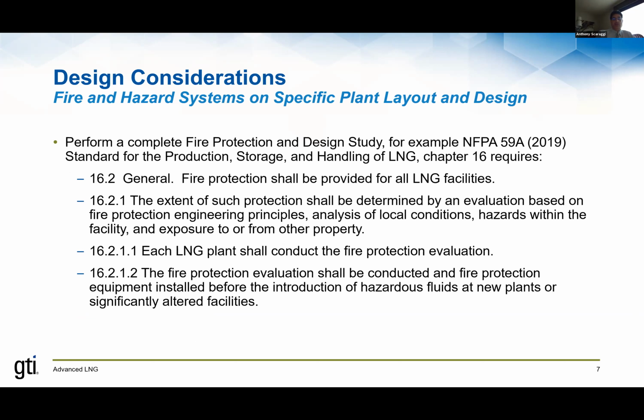Okay, a major consideration in LNG facilities is the whole fire protection system. LNG facilities, whether they're receiving terminals that do not make their own LNG, or whether they're a facility that actually takes natural gas and turns it into liquefied natural gas, meaning an export style or liquefaction facility, have many components that are needed for fire protection, and a fire study done, taking the full design of the plant into consideration, determining where those different components of a fire detection system should be located based on the design of the facility.